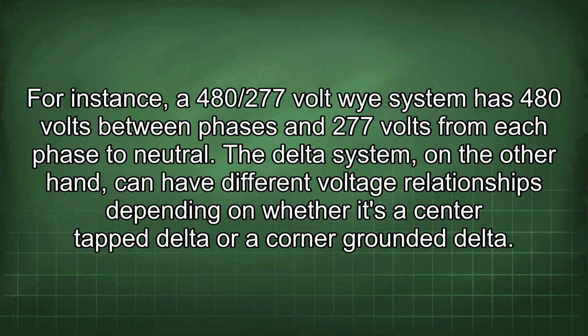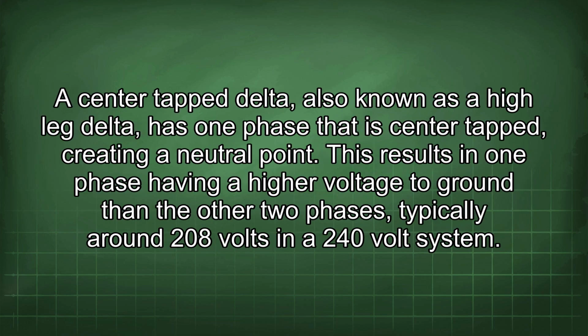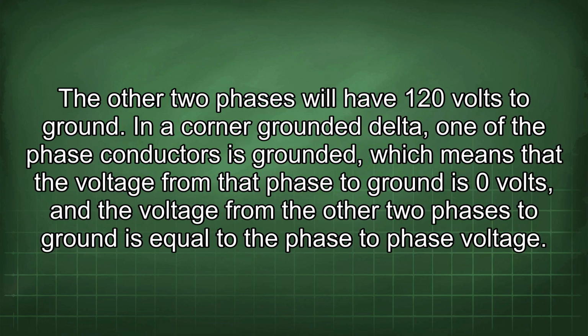The delta system, on the other hand, can have different voltage relationships depending on whether it's a center tap delta or a corner grounded delta. A center tap delta, also known as a high leg delta, has one phase that is center tapped, creating a neutral point. This results in one phase having a higher voltage to ground than the other two phases, typically around 208 volts in a 240 volt system. The other two phases will have 120 volts to ground. In a corner grounded delta, one of the phase conductors is grounded, which means that the voltage from that phase to ground is 0 volts, and the voltage from the other two phases to ground is equal to the phase-to-phase voltage.